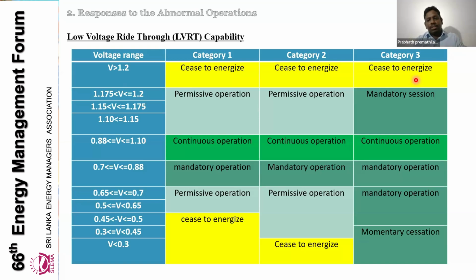There are some conditions they have to follow. Likewise, in the voltage disturbance ride through facility, the voltages are shown here. The more important thing is the voltage: we can define this range as 0.88 to 1.1, as per our available guideline. In that range, the solar PV inverter shall operate continuously. It is in the normal operation mode.